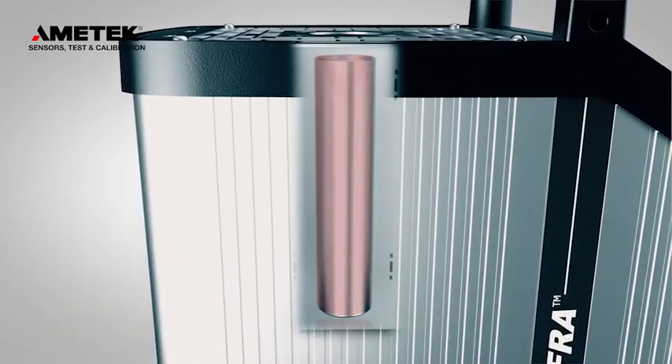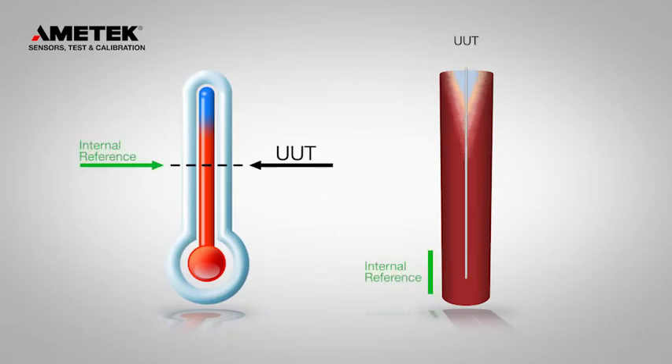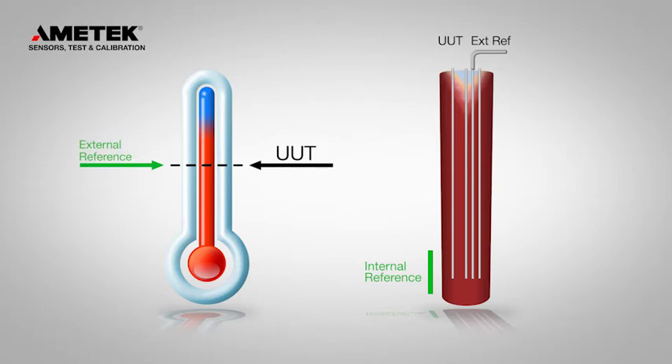The external reference sensor is perfect for higher accuracy or to reduce the effect of mass loading. The axial temperature gradient can be affected when calibrating large or multiple sensors. The external reference sensor compensates for the mass loading effect, and the CTC will even use the reference sensor to control the temperature in the insert.